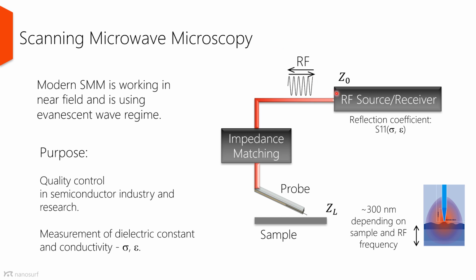Then the wave travels down through the impedance match, because the source has usually 50 ohm impedance and the tip-sample contact has much higher impedance. And these two have to be interfaced somehow. And I will talk about it a bit more a few slides later. And then the wave enters the probe, goes down to the tip, gets reflected back, and travels the same path back to the receiver. So there it is registered, and the reflection coefficient is calculated by comparing the amplitude of the received and the transmitted waves.